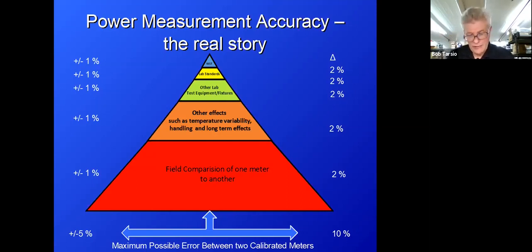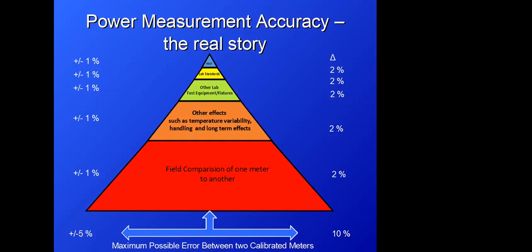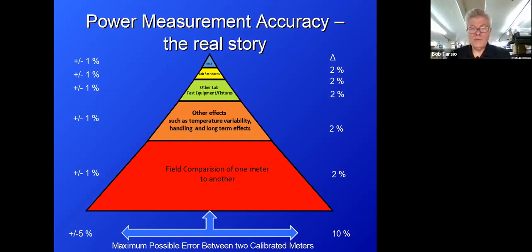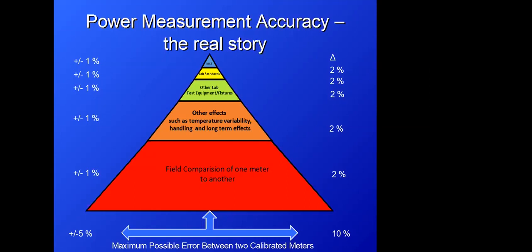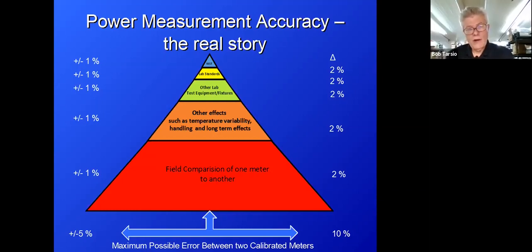Now, what is a lab standard? And that's what we use here at BDI to calibrate your power meter, your RF sensor, at least the RF sensor part of it, because there's 2 parts of the calibration, and I'll talk about that in just a second. Well, there are two principal methods for secondary standards that are used.